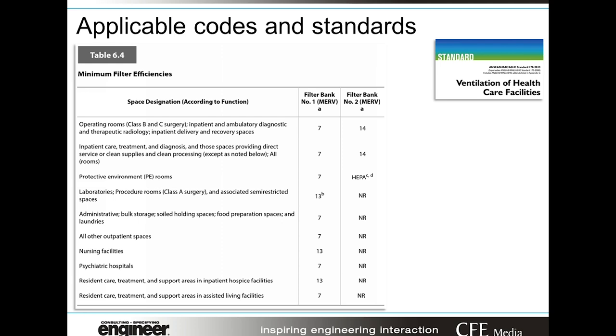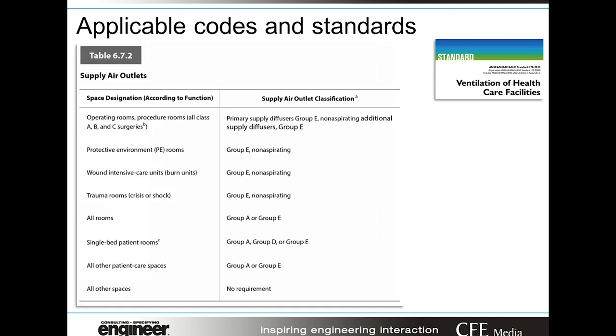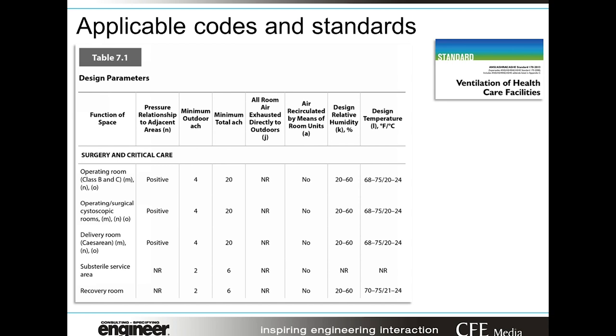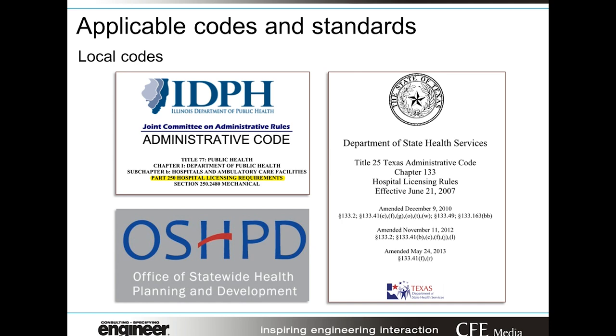ASHRAE Standard 170 provides simple tables that define various spaces within the facility and expectations for filter requirements, outlet and inlet positions, and air change rates, both from direct outdoor air and within the space. Some states such as Illinois, California, and Texas have not adopted FGI as a guideline and have published their own articles, guidelines, standards, and codes for ventilation in healthcare facilities. Many are adaptations of FGI and ASHRAE 170, but the bottom line is it's very important to understand where the facility is located and what standards and codes are applicable.